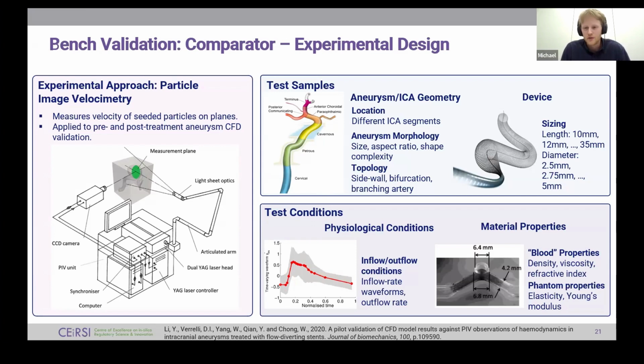And then for the device, you could investigate different sizes of device. Test conditions then refers to physiological conditions, which are typically imposed through different flow rates. And then material properties, where you will need to choose some kind of fluid that represents your blood, that'll have a specific density, viscosity, refractive index, and then also properties of the phantom aneurysm model itself. So whether or not you include anything like elasticity, that might be important as well.